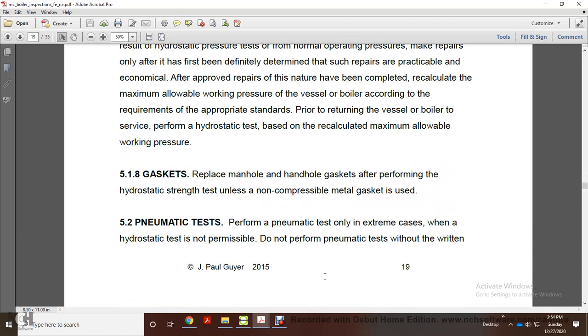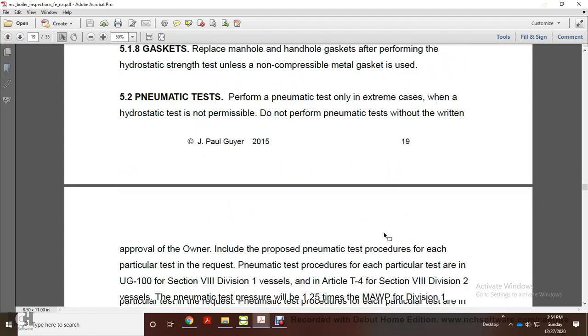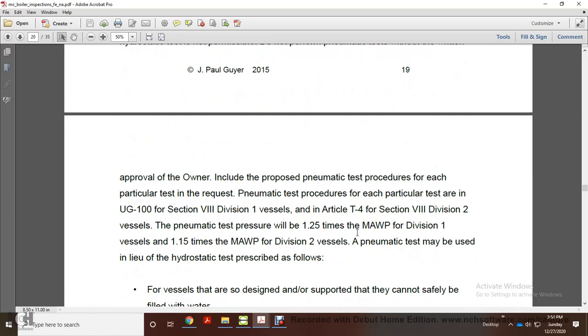5.1.8 Gasket: replace manhole and handhole gaskets after performing hydrostatic strength tests, unless non-compressible metal gaskets are used. Pneumatic tests: perform a pneumatic test only when a hydrostatic test is not permissible. Do not perform pneumatic tests without written approval from the owner of the proposed pneumatic test procedure for each of the particular tests in the request.